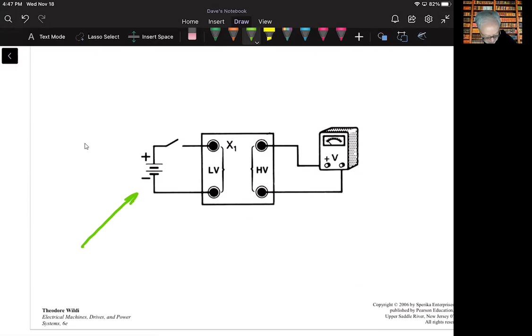The transformer terminal connected to the positive side is marked X1. A DC voltmeter is connected across the high voltage side. When the switch is closed, a voltage is momentarily induced into the high voltage winding. At that moment, because it's DC and transformers aren't designed for DC, if the pointer of the voltmeter moves upscale, the transformer terminal connected across the positive terminal of the voltmeter is marked H1, and the other one would have to be H2.